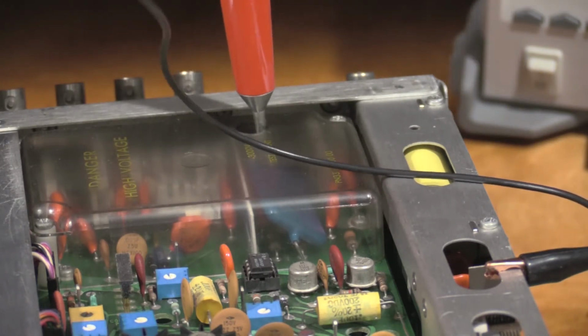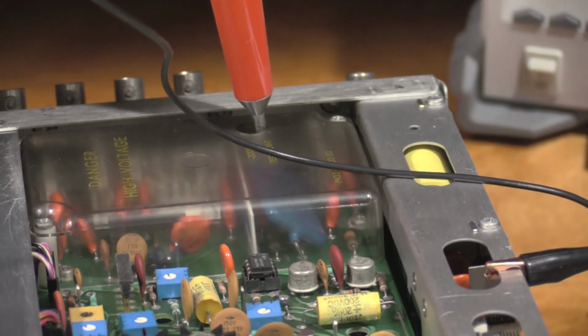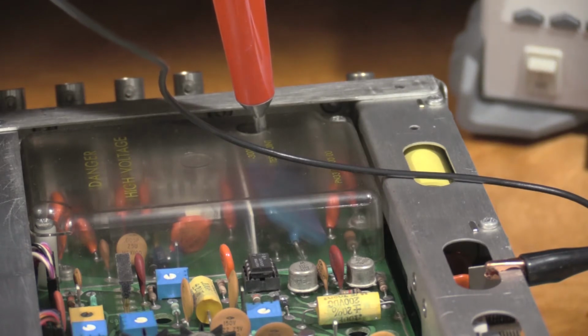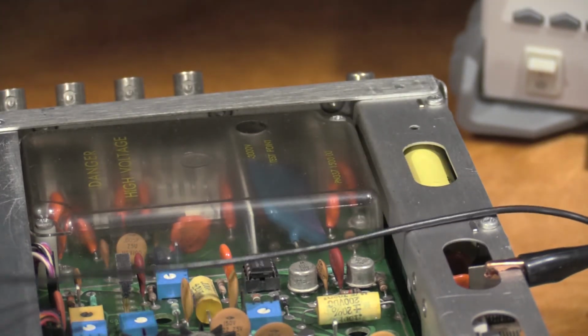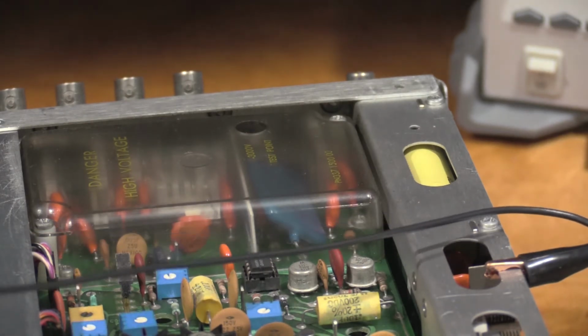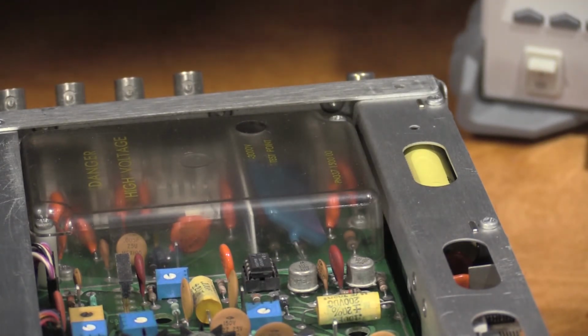A little bit of corrosion. All right. So it's not possible for me to move the camera, but I am at 2,978 volts, so that is fine. I had to rotate the tip of the probe to clean it up. Either clean some tarnish off the tip of the probe or clean some tarnish off the joint so I can get a good measurement. Because even with 3,000 volts, I was still having a high impedance connection and it wasn't going to the meter correctly. But high voltage is good.